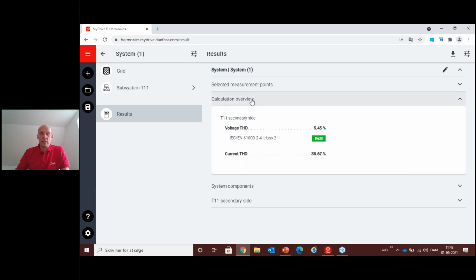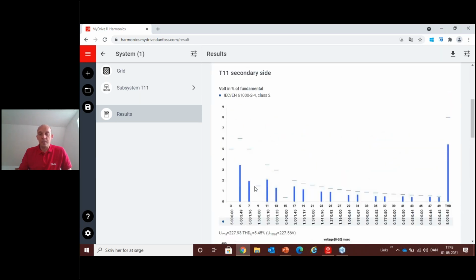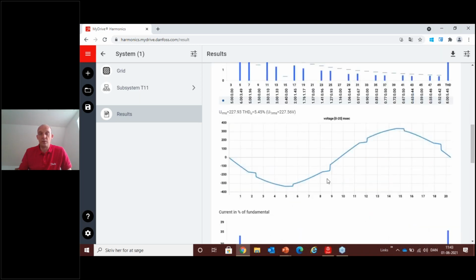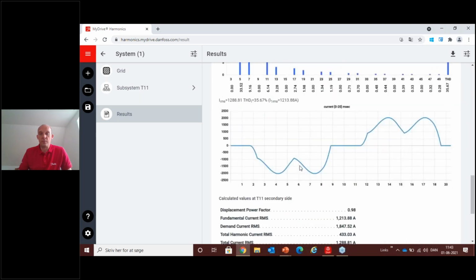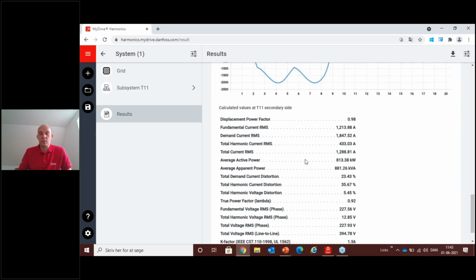What the calculation overview tells me is I have a voltage distortion of 5.5%. I do comply with the EN 61000 standard. I have a current distortion on the transformer equal to 35%. I can also look at the individual harmonics. I can see how big the fifth is, how big the total harmonic current distortion is. I can see the current waveforms, the voltage waveforms, and so forth. All data that can be relevant to show and to know a bit about for your installation.